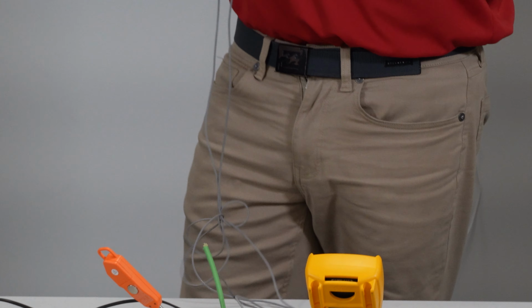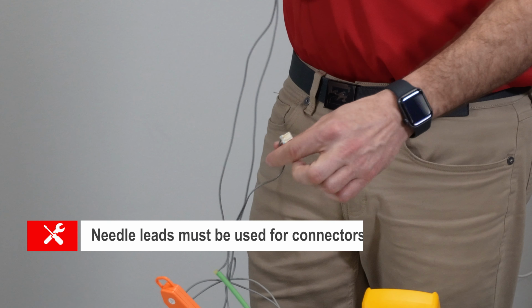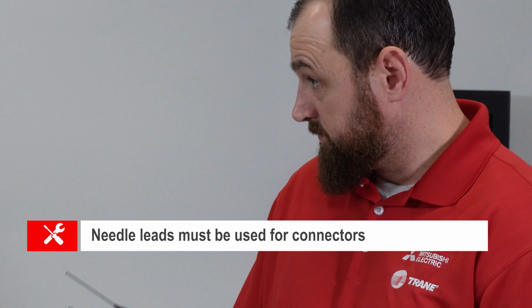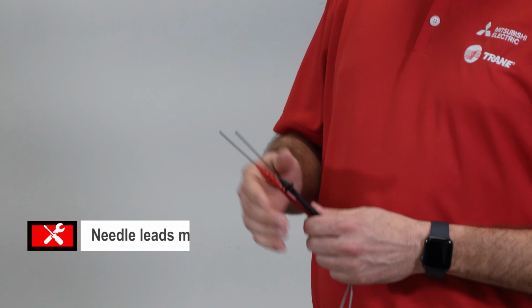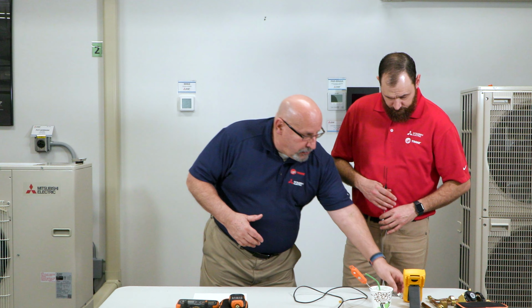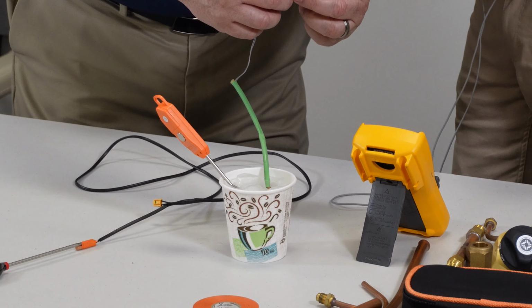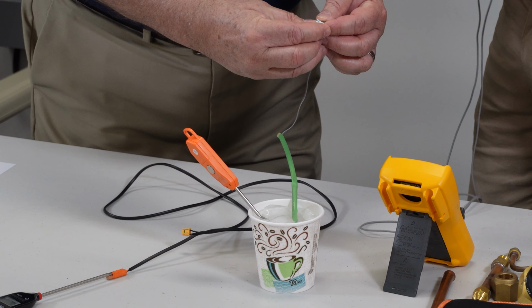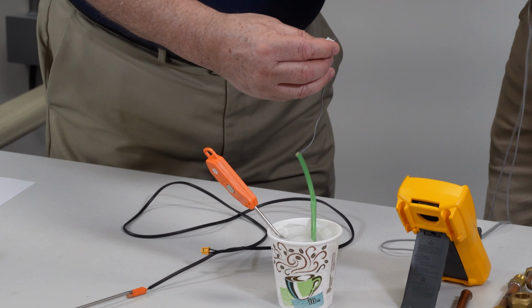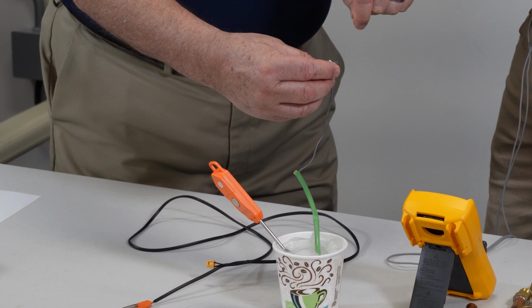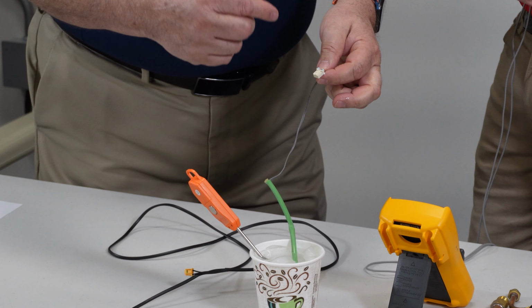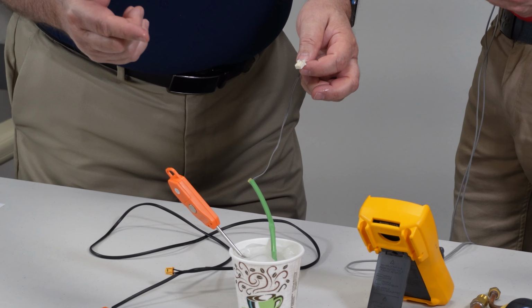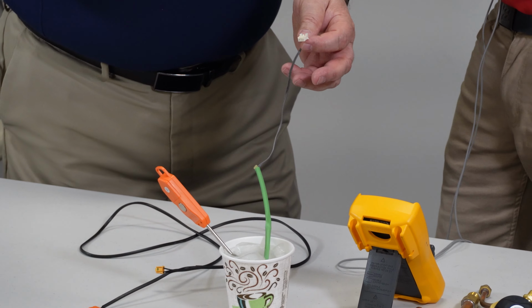Now, again, to point out, for our connectors, we have to use needle leads. Absolutely. Do you know why we have to use these versus the other? Yeah, because the standard leads that you get with a meter are much thicker. So if you look at this connector, the openings that you have to put them in are very small. Correct. And only the needle leads will fit in there. If you try to force a standard lead, you're going to break the connector or break the socket that it's plugged into at the board, and you're going to have to buy a new thermistor or a new circuit board.